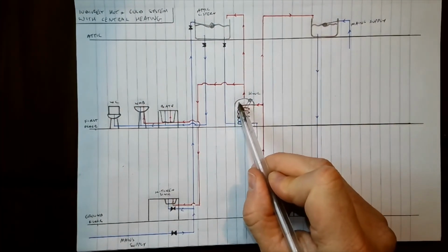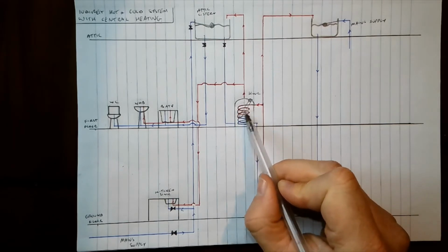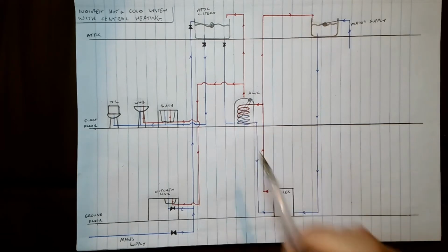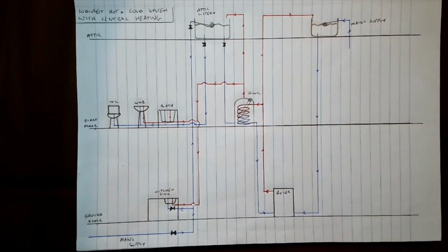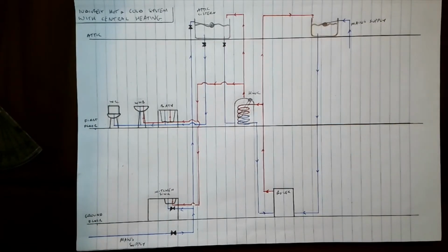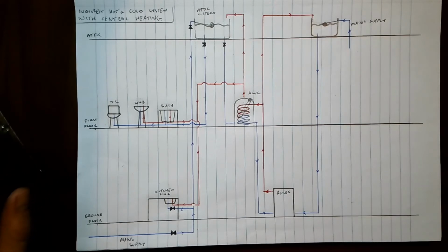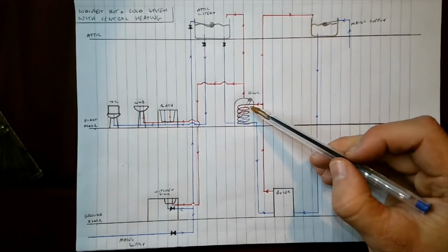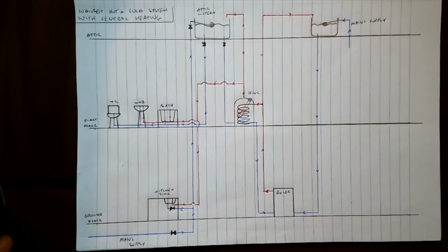So again, the water in the cylinder is being heated by either the coil or the immersion. That coil is more efficient, less demanding on the system. That's usually what's used. So when the heating is on in your home, that's constantly heating the water. But sometimes if the heating has been off, maybe in the summertime you're not using the heating and you want the quick heating of the water, so you can have a shower or a bath or whatever, you might turn on the immersion in that case. Okay.